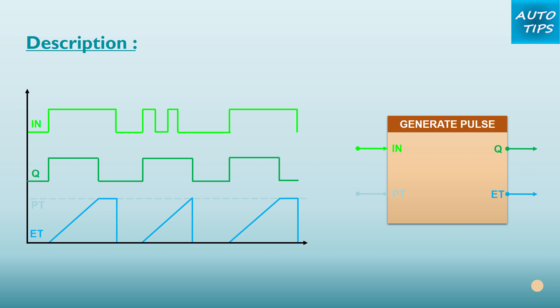The preset time PT begins when the instruction starts. Output Q is set for the duration PT, regardless of the subsequent course of the input signal. While the time PT is running, the detection of a new positive signal edge at the IN input has no influence on the signal state at the Q output.